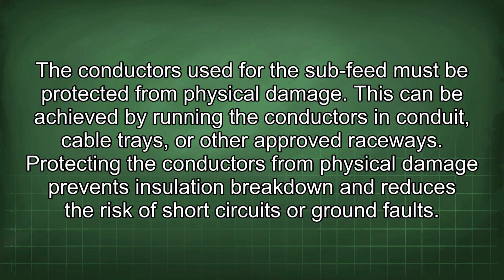The conductors used for the sub-feed must be protected from physical damage. This can be achieved by running the conductors in conduit, cable trays, or other approved raceways. Protecting the conductors from physical damage prevents insulation breakdown and reduces the risk of short circuits or ground faults.